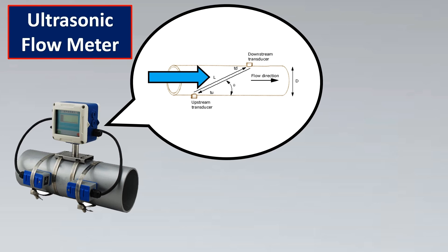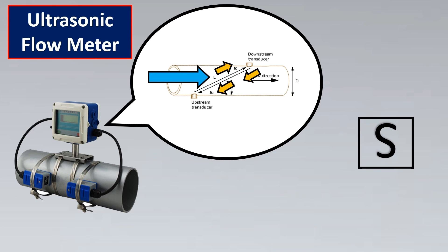For an ultrasonic flow meter, an ultrasonic wave travels faster in the direction of flow and takes more time when traveling against it. The time difference indicates the increase or decrease in flow. Because the ultrasonic signals are the most important element, they are represented as 'S' in the P&ID symbol, standing for those ultrasonic waves. This is the P&ID symbol for an ultrasonic flow meter.